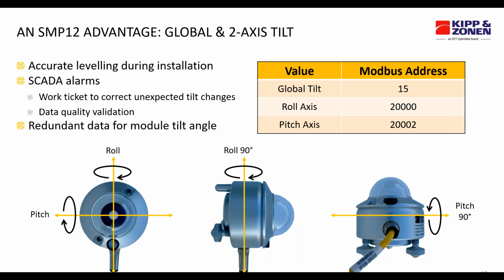You can see in these diagrams how those two measurements rotate with the sensor. So if you get a sensor on your desk and connect it to Smart Explorer or Modbus Poll or something like that, where you can see roll and pitch values, you can rotate around the cable axis or perpendicular to the cable axis and get a feel for how to control the sensor orientation using these two different axes.